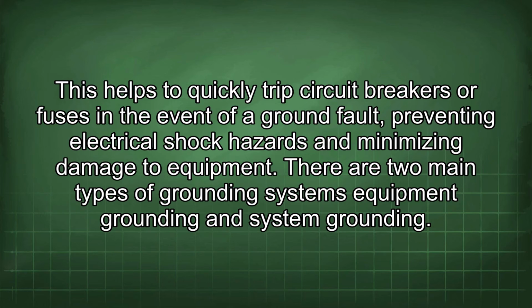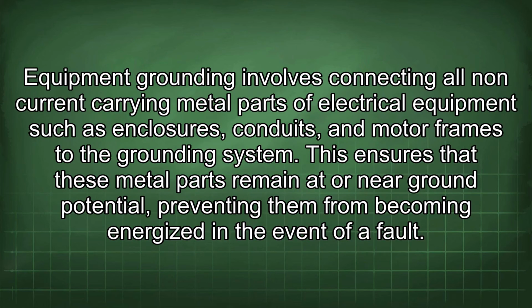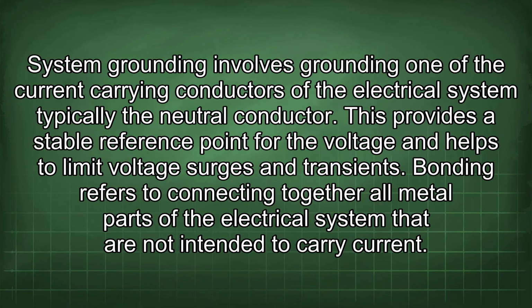There are two main types of grounding systems: equipment grounding and system grounding. Equipment grounding involves connecting all non-current carrying metal parts of electrical equipment, such as enclosures, conduits, and motor frames, to the grounding system. This ensures that these metal parts remain at or near ground potential, preventing them from becoming energized in the event of a fault. System grounding involves grounding one of the current carrying conductors of the electrical system, typically the neutral conductor. This provides a stable reference point for the voltage and helps to limit voltage surges and transients.